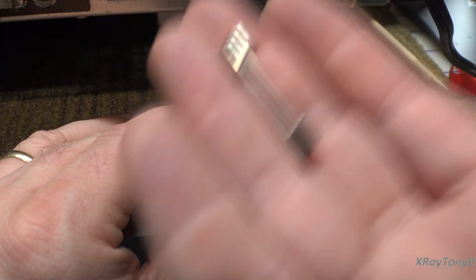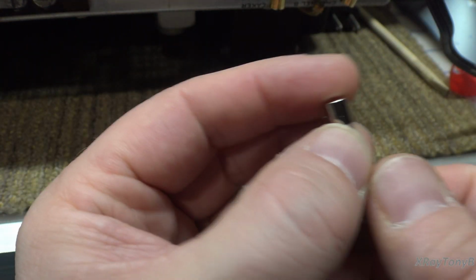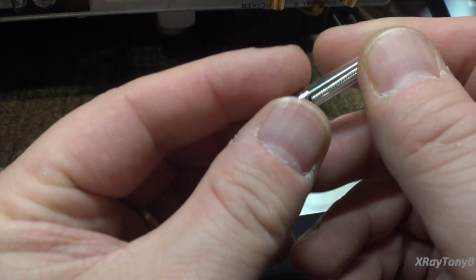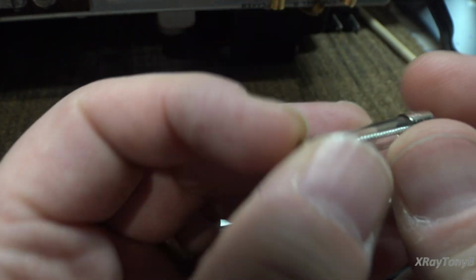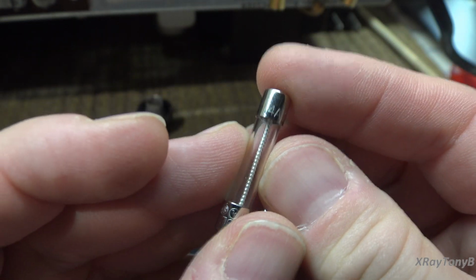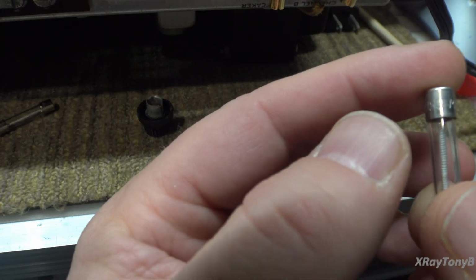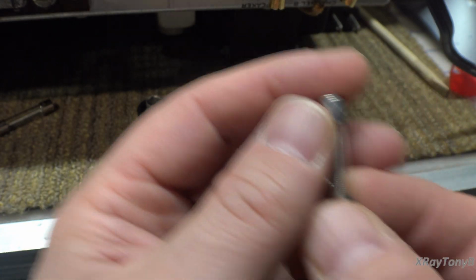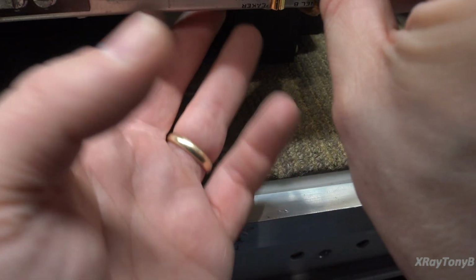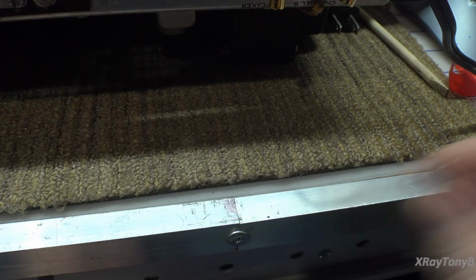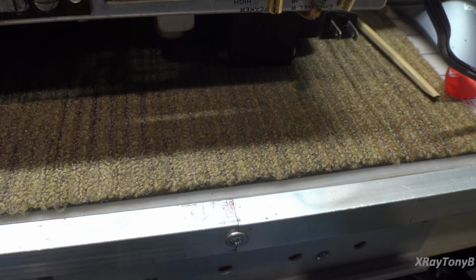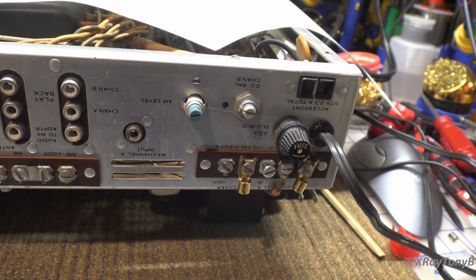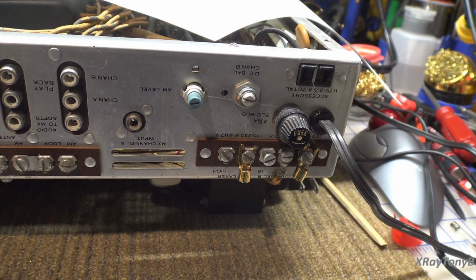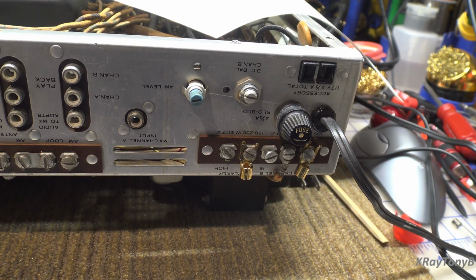Another reason you always start off with a dim bulb checker is if you forget to check who changed the fuse last. This is supposed to be a 2.5 amp slow blow fuse, and yeah, they put a 4 amp in there. I don't have any 2.5s, I'll have to get some more, but I do have some 2 amp slow blow, which will be fine for test purposes since we're not going to run this at high power until it's working. That should be good enough, because we're not letting this thing off the leash until we know all the power supplies are good and there are no shorts.